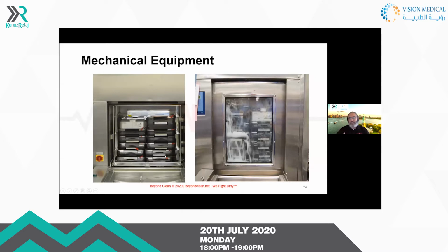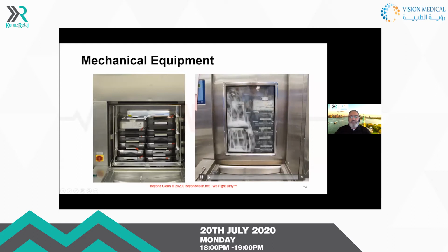So we know that the cleaning process is not being followed. As well, there is always a shelf in the middle with another sprayer arm that they removed to fit more trays. So I encourage them to let them know that this is not cleaning the way that it should. And I asked them why they did it. And they said because of the pressure that they received from the operating room theater to get instruments to them. And I said that they do not want to do this because these instruments are not clean. And again, if we go back to not clean, they're not sterile. I will move quickly because I don't want to hold you up.